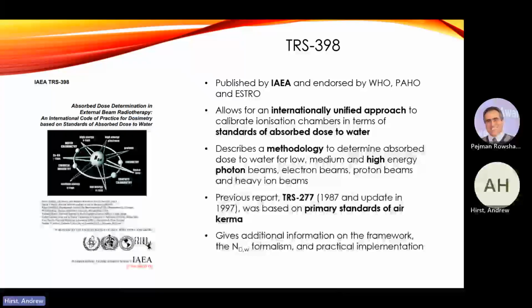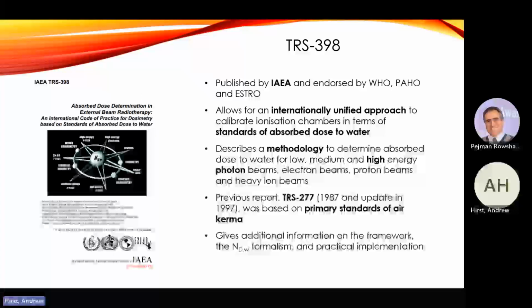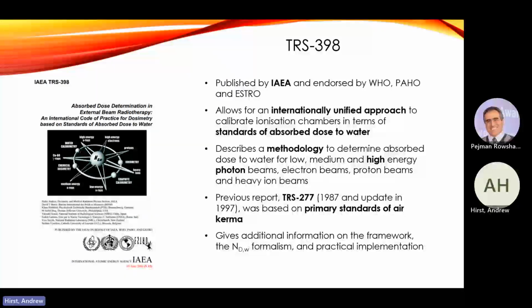It supersedes a previous report, TRS 277. So we used to have a primary standard based on air kerma, not absorbed dose to water. And so there had to be a conversion between air kerma and absorbed dose to water in the clinic. And it was a lot more laborious to actually perform reference dosimetry. There's more uncertainties, it's less robust. So now we have this absorbed dose to water standard from a while ago. I mean, 1998, I think, is when TRS 398 first came out, and they're updating this. It should probably come out in the next few months with a bit of an update, and a few things will be clarified in it. Did I miss anything? No, it's got other beams, electron beams, proton beams, heavy ions, but we're just focusing on photons now.